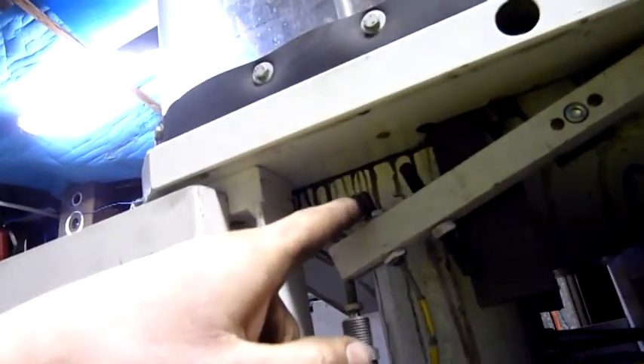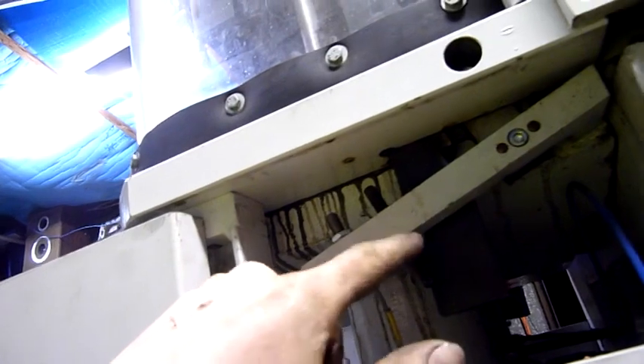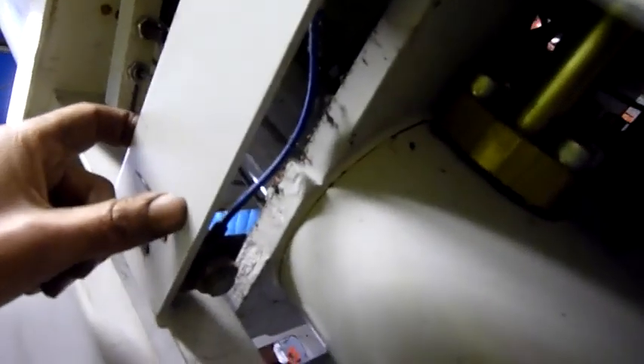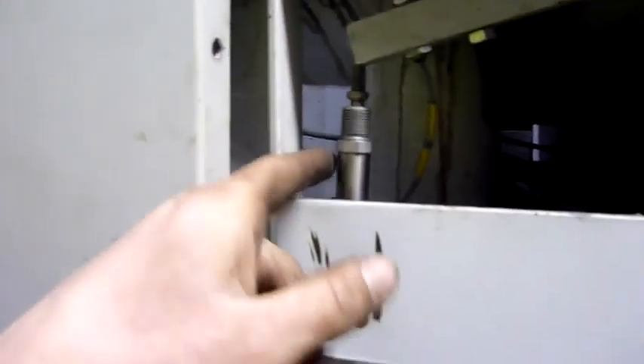There's a little SMC pilot valve. And that goes to this little cylinder here. That's what toggles it. Jesus, barely making contact. Oh, it's got a proximity sensor on it as well to tell it when it's disengaged, as well as a stop screw. Yeah, spring return, or just gravity return, single acting cylinder.